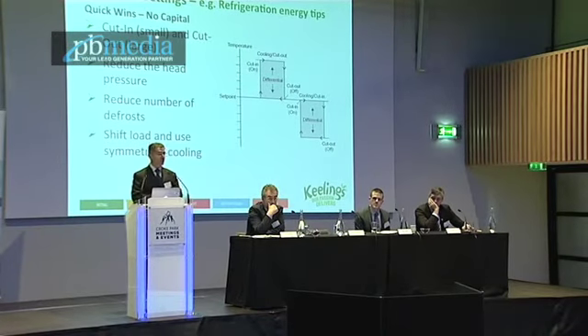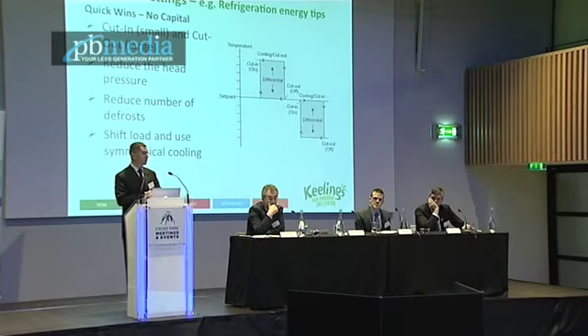In the cut-out control mode, always strive to have the differential temperature above the set point as high as possible, preferably at 2 degrees Celsius, which will buy you more free time from the fans, off time. On the other hand, with the cut-in mode, always strive to have the differential temperature as small as possible to reduce the amount of time that the fans are running.